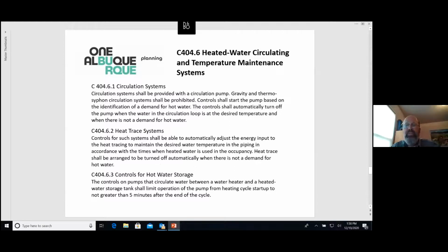Heated water circulating, temperature maintenance systems, circulation systems. Basically, you need a pump, a circulation pump. The gravity thermosiphon circulation, you can't do that anymore. I don't know the last time I saw one of those, but somebody may want to design one, but can't anymore. It's going to have controls that start the pump based on the identification of the demand for hot water. Controls turn the pump off when it reaches a desired temperature or when there's no further demand for the hot water.